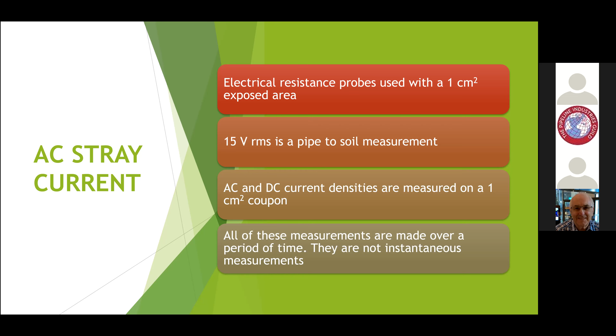Actually, the smaller the steel, the higher the resistance. So if you had a coupon of 1 centimeter square and it corroded, its surface area would decrease, so its resistance would increase. By doing some fancy measurements, we can calculate what the corrosion rate is. With the electrical resistance probe, you can also measure the actual corrosion rate, the AC and DC current densities, and the ratios between the AC and DC current densities. So corrosion probes are one way to deal with it.